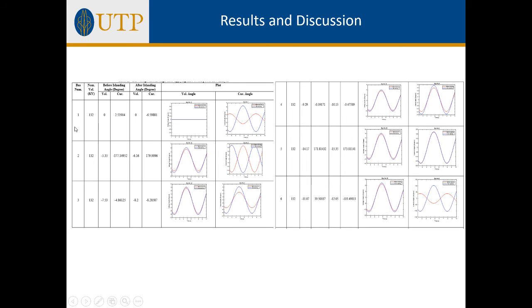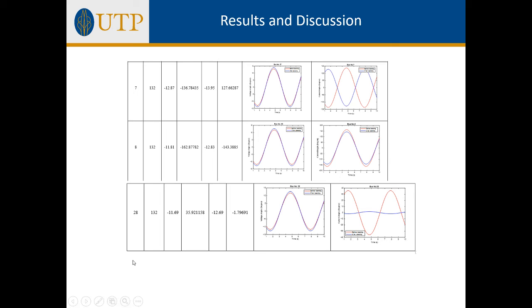So you can see that this is bus number 1, where the voltage angle remained the same, because bus number 1 is the slack bus. So the voltage angle didn't change, but the current angle changed. And if you look at other buses, you will definitely see that the angles are changing before and after islanding, which is really not expected, because we need to keep the system stable during and before the islanding. So those are the data of each and every bus before and after islanding, and all the data are showing that there is some unstable situation when the microgrid goes to islanding.